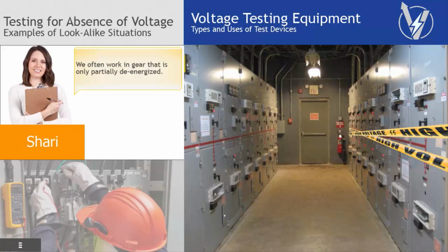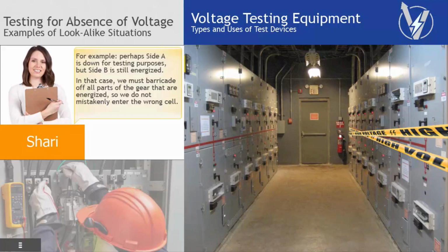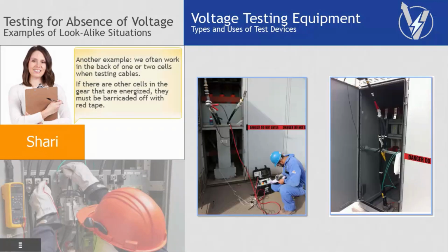We often work in gear that is only partially de-energized. For example, perhaps side A is down for testing purposes, but side B is still energized. In that case, we must barricade off all parts of the gear that are energized so we do not mistakenly enter the wrong cell. Another example: we often work in the back of 1 or 2 cells when testing cables. If there are other cells in the gear that are energized, they must be barricaded off with red tape.